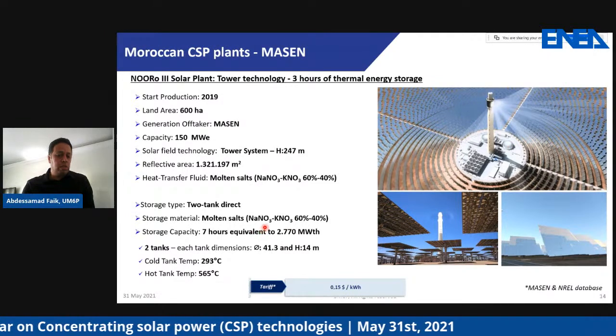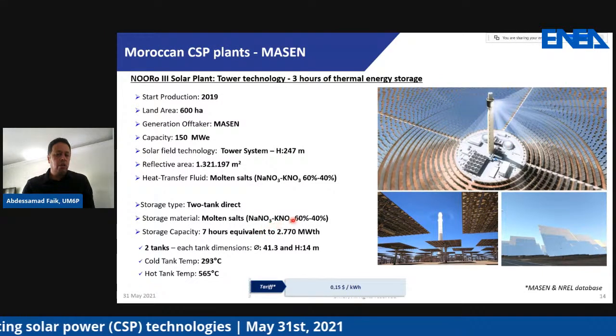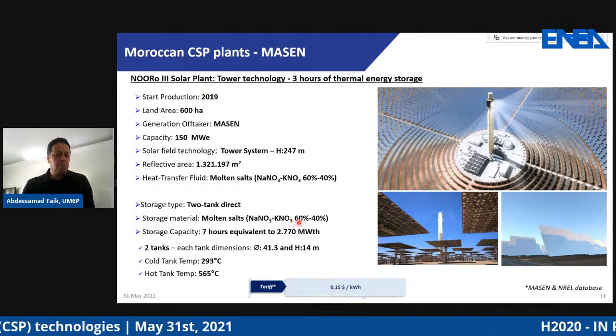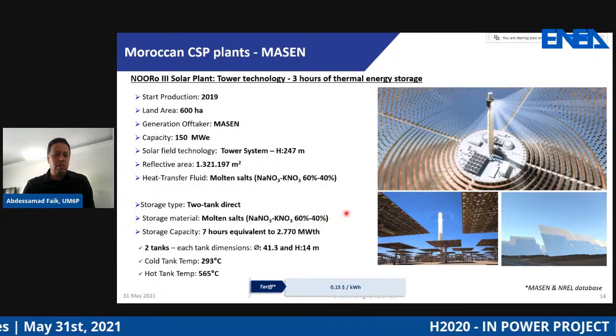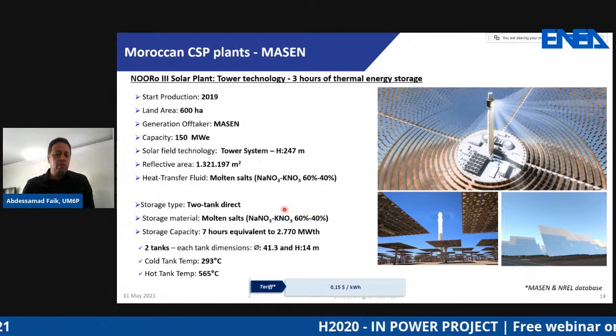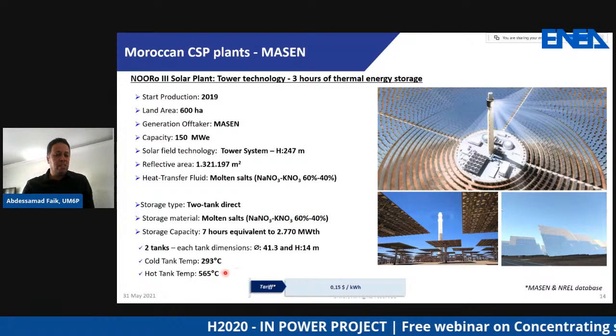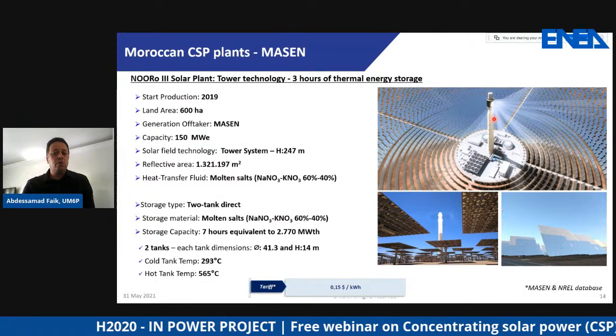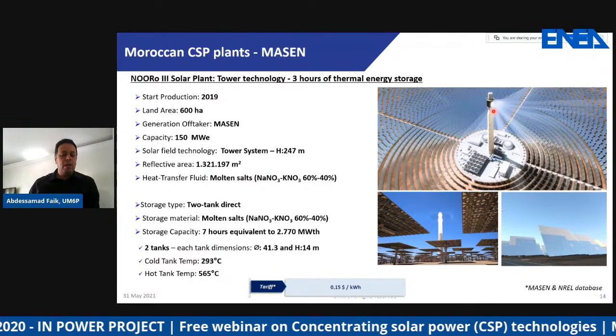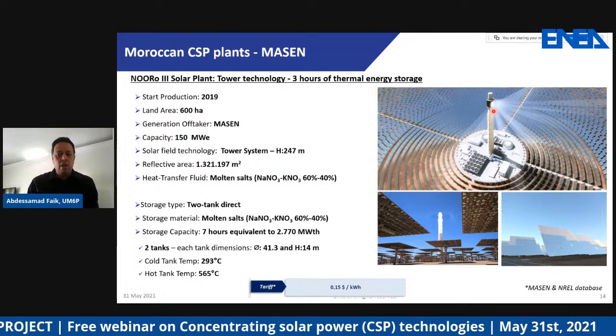The molten salt we use is always the same, based on sodium nitrate and potassium nitrate at 60 weight percent and 40 weight percent. The decomposition temperature of this salt is around 565 degrees, which is why we use a maximum temperature of up to 565 degrees in this power plant.